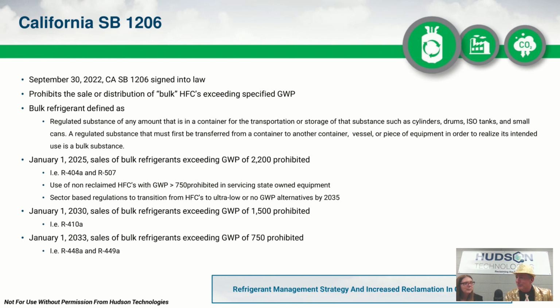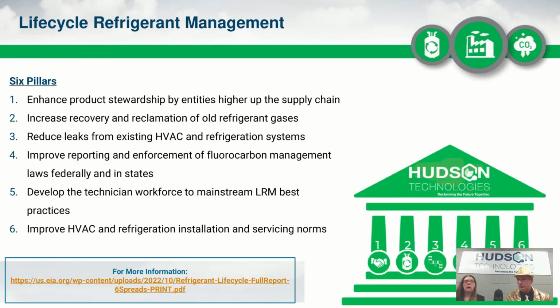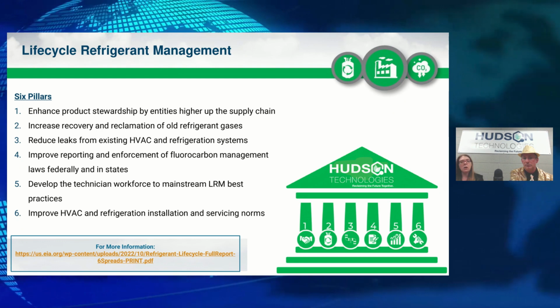But California considers essentially any packaging of refrigerant to be bulk. So a 24-pound, 25-pound, 30-pound disposable cylinder is covered under this regulation, because under the California definition, that's bulk refrigerant. Even a standard box of refrigerant from the parts counter, from your parts wholesale supply, is covered.